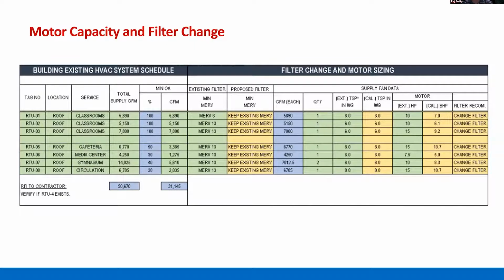So most of the time, with the horsepower of the fan motors, we have some spare capacity. So you can theoretically do this immediately. And then as you start to see some degradation in the performance, you can go back to the previous filter size. These are pretty straightforward calculations to run, and then you can know which type of filter. So we are putting in anything from MERV, and we'll go up a couple of MERV sizes and try to reach that MERV 13. So just create a basic filter motor change.